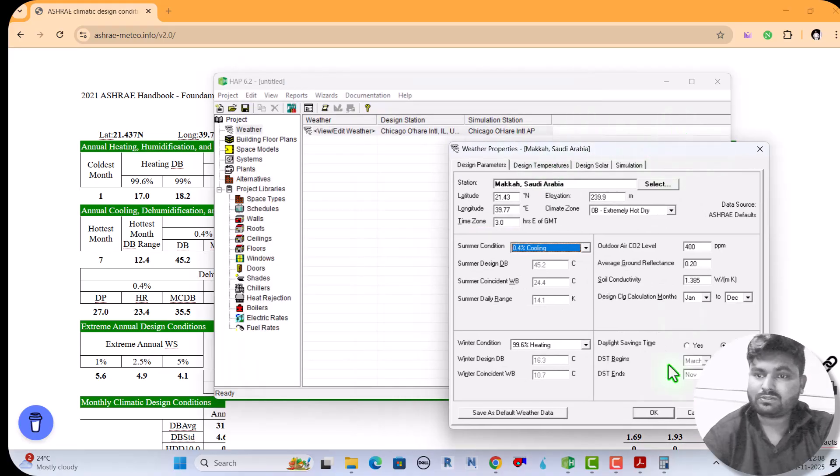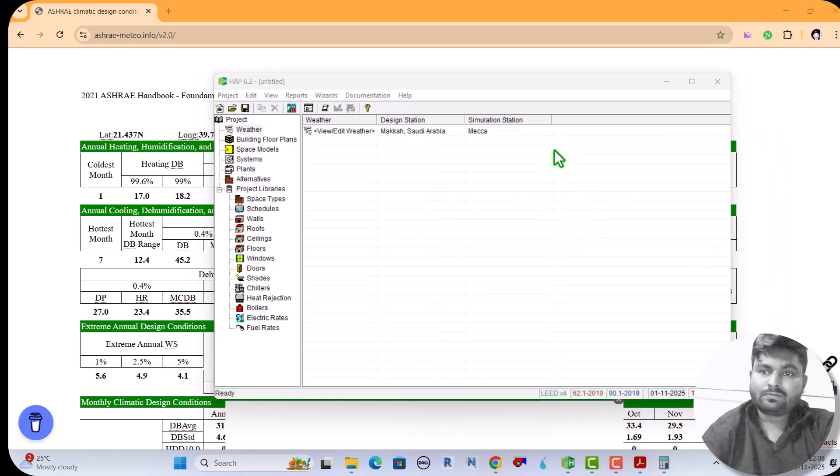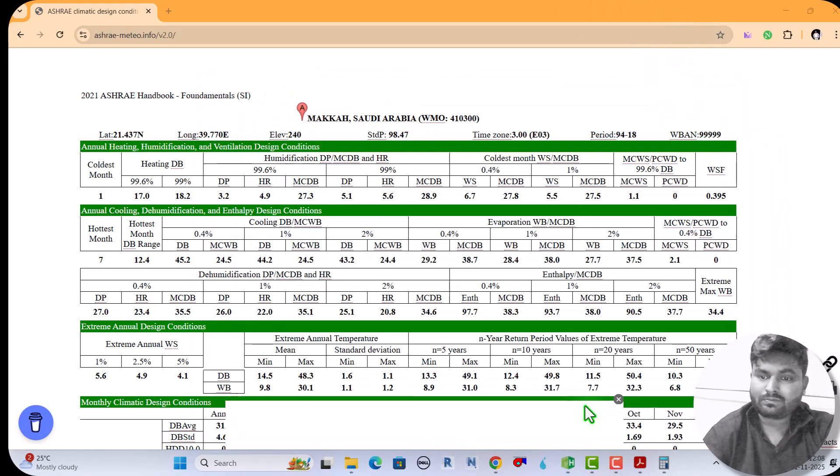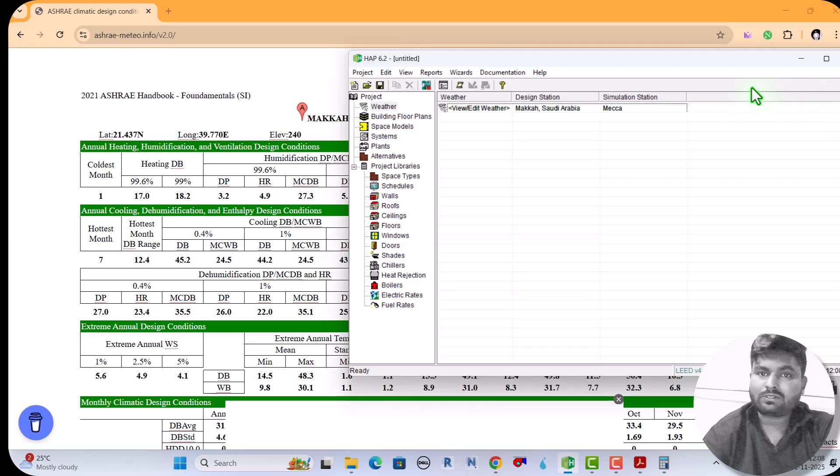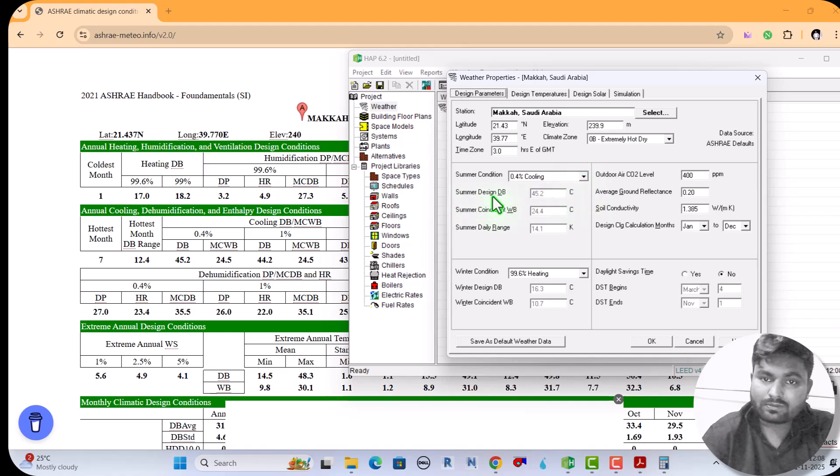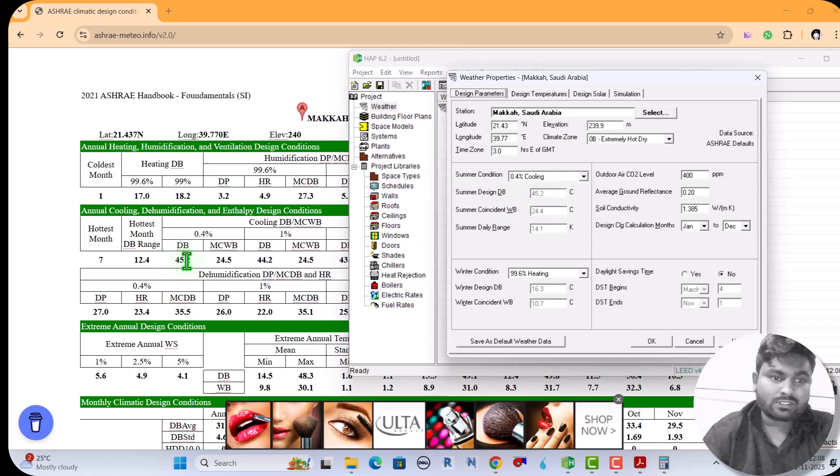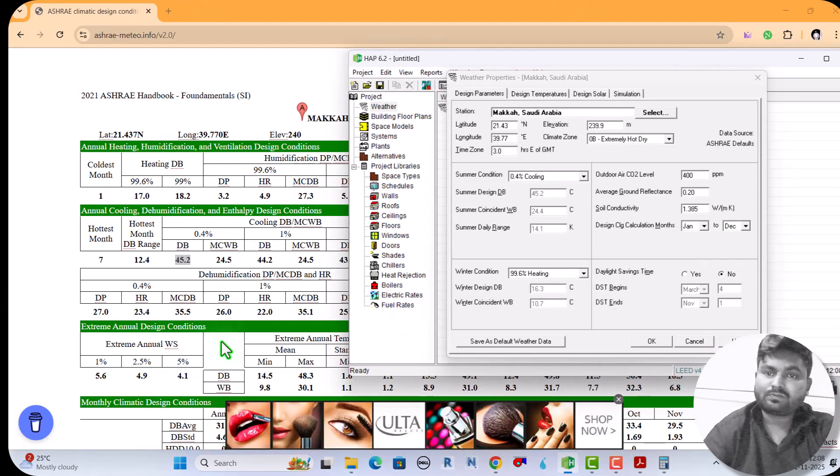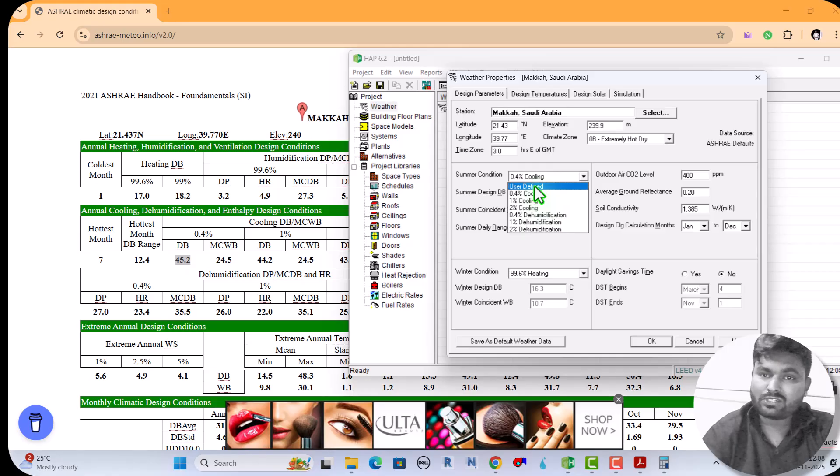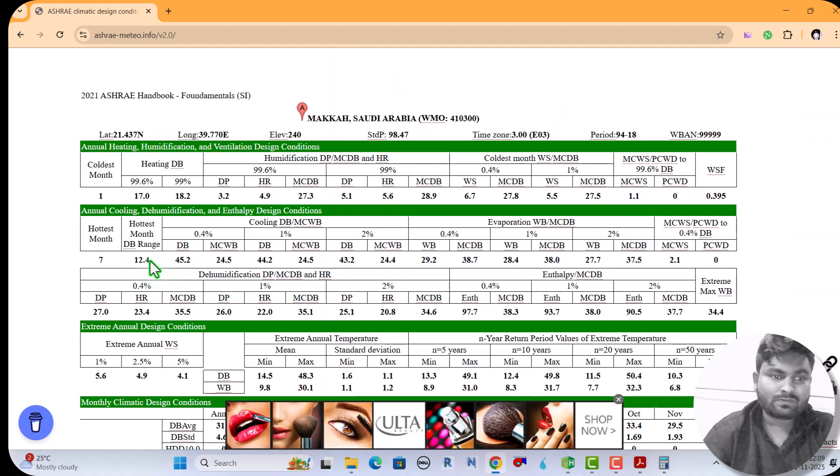See, the summer dry bulb design temperature is 45.2, which is here also 45.2, so it's good. Now summer coincident wet bulb, here is 24.5, here is 24.4. It is fine but if you want to change, just go to user defined and here you can change 24.5. Summer daily range here is 14.1, dry bulb range is 12.4, so 12.4 you can do.